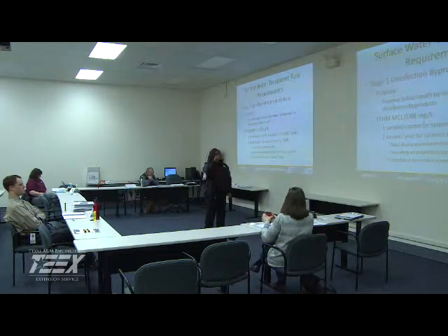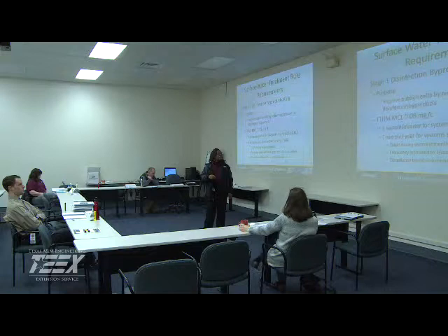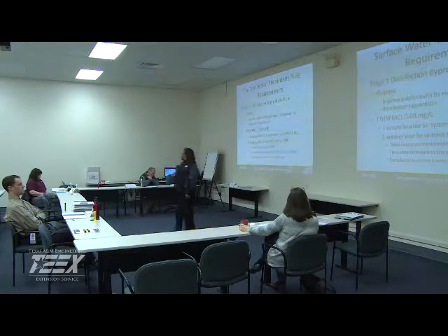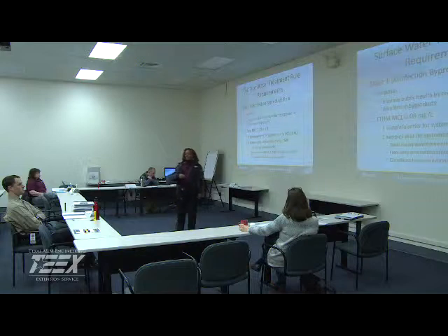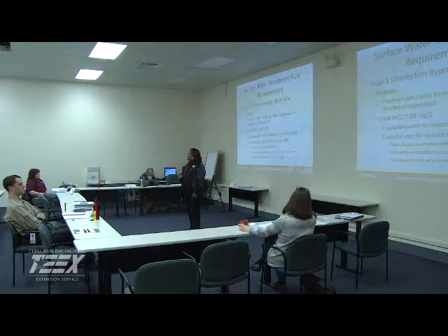We're pulling 1 sample per quarter for systems 500 to 10,000, 1 sample per year for systems less than 500. Now, with the systems that are pulling the 1 sample per year, the stipulation is they want it taken during the warmest month of the year, not during the coldest. And if you're exceeding that MCL, now that has just been increased to 1 per quarter.